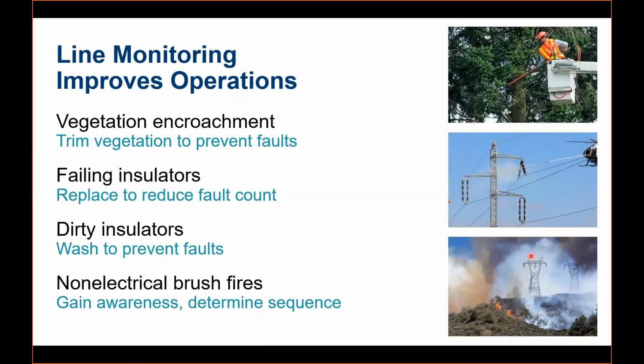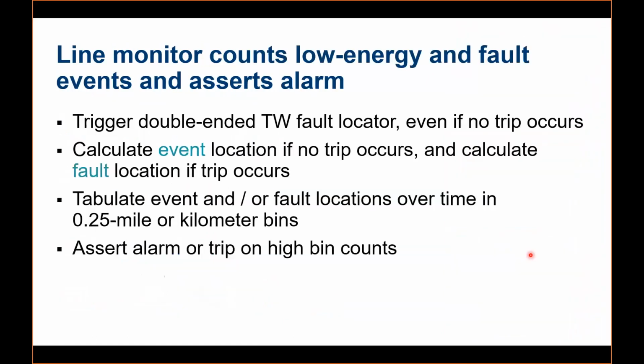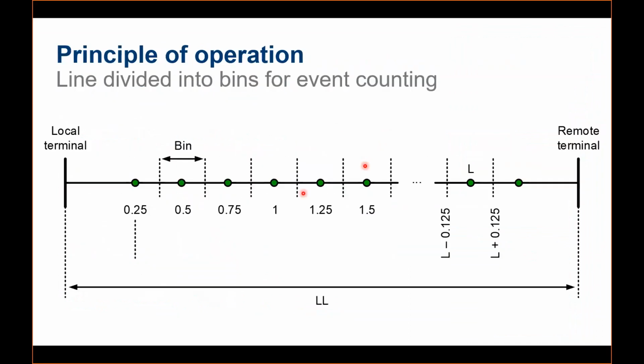So in the relay, we have a line monitoring element, which again uses the double-ended traveling wave fault locator. This is the most effective method to pinpoint where you have low energy events, and the relay will divide the line into sections.